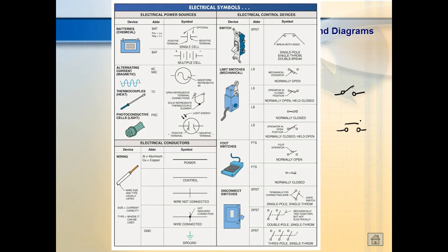The advantage of a double break is you've got two chances of breaking the circuit. Plus the way the double break works, it's on a tilt, so if one side breaks loose, it'll come up, and that will almost always break the other contact too. So these double break contacts are less susceptible to welding together. Most of your relays have double break contacts, not all of them, but a lot of them do. These little control relays we'll be using are not double break contacts.